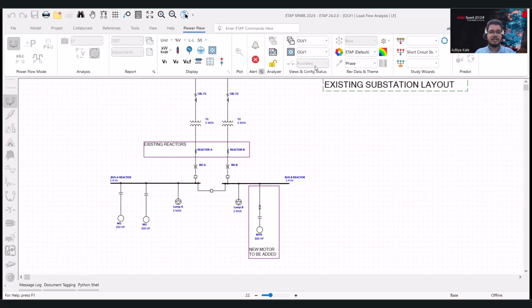In a parallel configuration, we have the same case. However, in the single-ended scenario, which is the worst case for us, the motor initial voltage drops drastically to 82.5%. In our project that we did, this number was close to 81%. The numbers are manipulated here for the sake of the presentation.